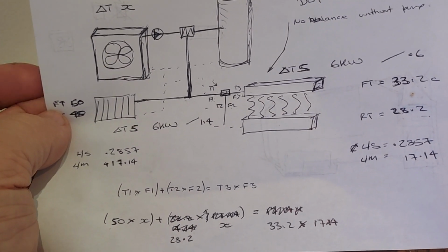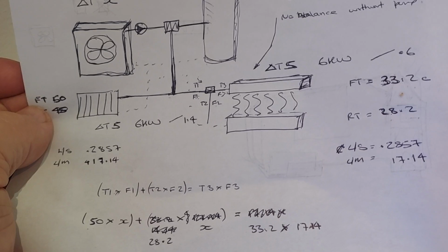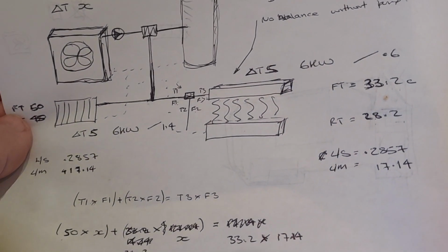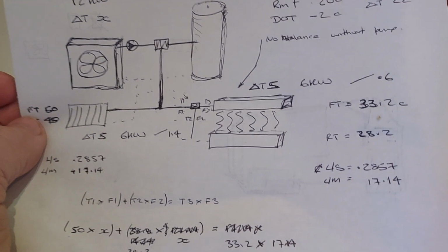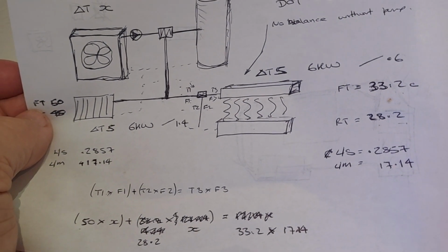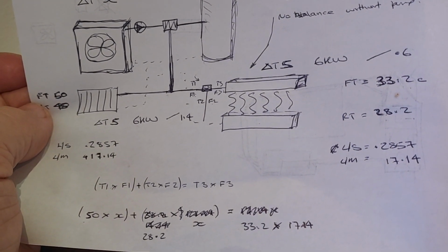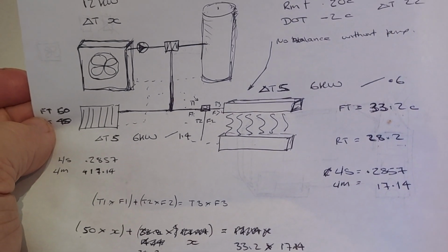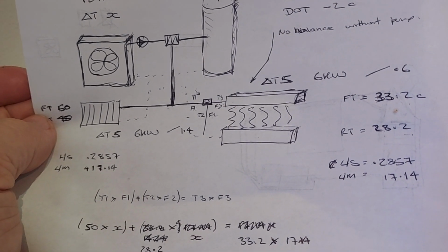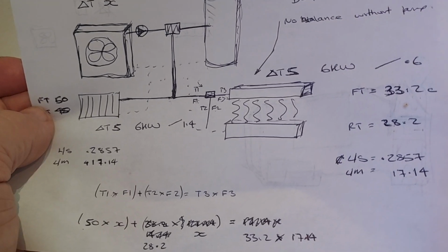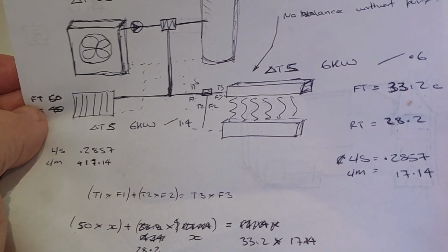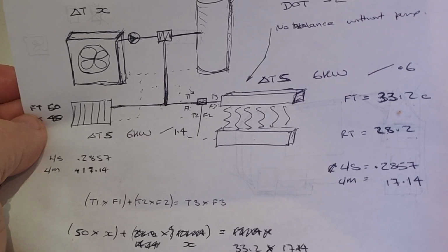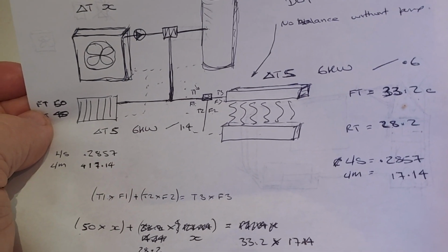And I've picked typical weather comp curves for these two systems. So I've gone with a 0.6 curve for the underfloor heating, and with a 1.4 curve for the radiators. So that would be a flow temperature at design outside temperature of -2 of 50 degrees flow at the radiator. Remember, that's delta T5, so that's a mean water temperature of 47.5. And I've deliberately gone for that.